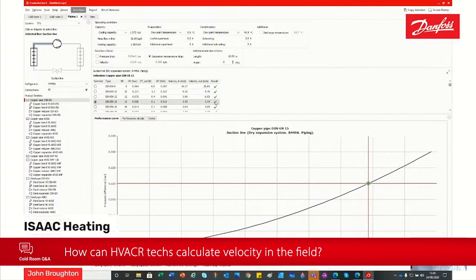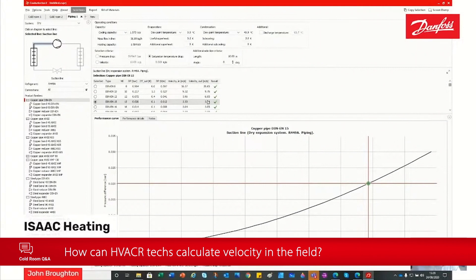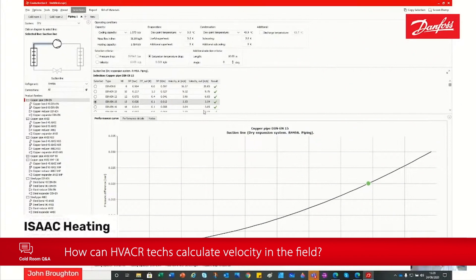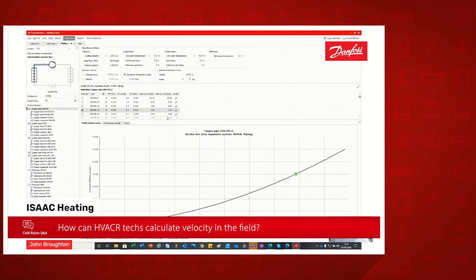It will basically give you — and you can see here it's highlighted 15 mil, and it's giving you a velocity. The velocity here is 3.5 meters a second. For a suction line, I think that's a little bit low; I'd rather be up at about 6 meters a second to get the oil back. The rule of thumb is that anywhere between 4 and 6 on a horizontal line is absolutely fine. I'd probably go to the 12 mil to get the velocity up a bit and get more oil back to the machine. It's a very quick and easy way to do it, and you can decide whether it's vertical, horizontal, and all those sorts of things.